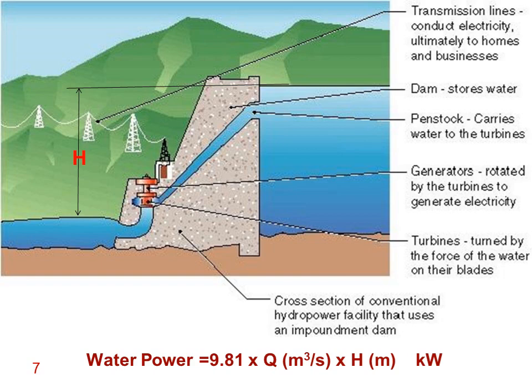The difference in water level between upstream and downstream is called H in meters, and the flow rate through the water channel inside the dam is called Q in cubic meters per second. If you multiply by rho times g — where rho for clear water is 1000 kg/m³ and g is 9.81 m/s² — and divide by 1000, it gives you the water power in kilowatts.